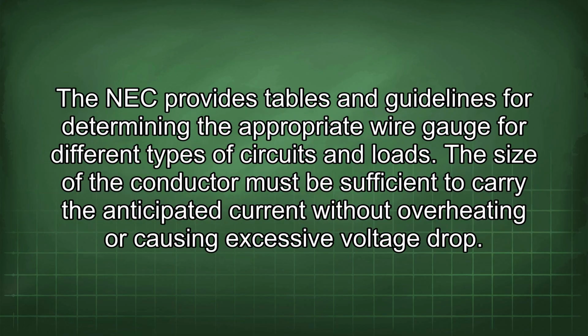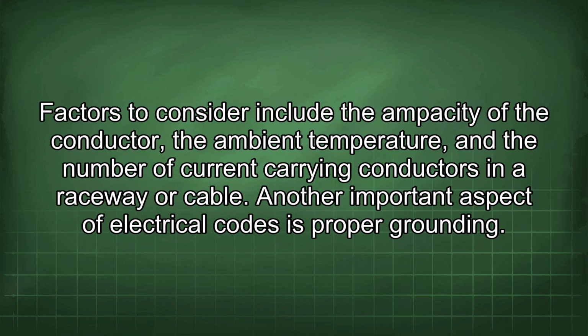The NEC provides tables and guidelines for determining the appropriate wire gauge for different types of circuits and loads. The size of the conductor must be sufficient to carry the anticipated current without overheating or causing excessive voltage drop. Factors to consider include the ampacity of the conductor, the ambient temperature, and the number of current-carrying conductors in a raceway or cable. Another important aspect of electrical codes is proper grounding.